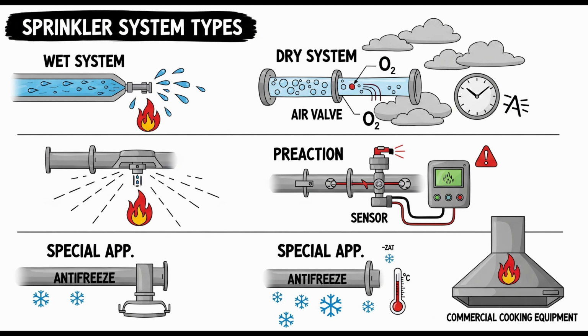Exactly. By the time a sprinkler head fuses from the heat, the pipe should ideally already be full of water, allowing immediate discharge. If the detector activated at the same or a higher temperature, there'd be a delay while the pipes fill, or the system might not function as intended, effectively becoming a slower, dry pipe system at that point. That's a clear engineering priority. Detection must lead the sprinkler activation for pre-action systems.